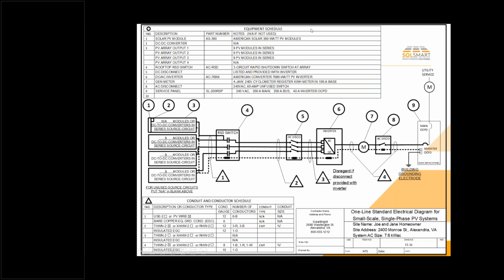And this electrical drawing is a standard drawing where I just went in and filled in the blanks. Okay, and so I've got a solar module, that's the AS360. 9 modules in series. That's for 3 different inputs into this inverter. It's got a rapid shutdown switch for compliance with rapid shutdown. All right, and it's got the American inverter, 7600 watt inverter. And then we're using PV wire, THWN-2 conductors for the conduit wire. So we got cables coming to the RSD switch, and then we have conduit wire with THWN-2 going from there. It's the type of wire. It's all 12 gauge wire coming up to the inverter.